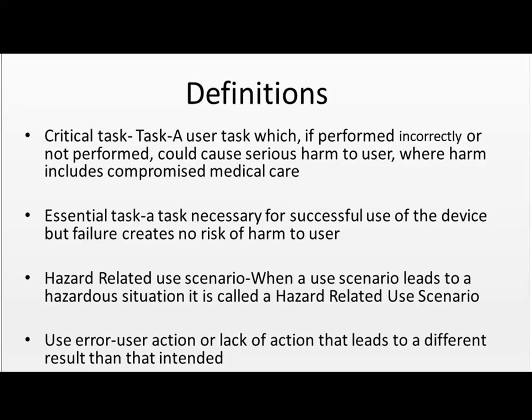A hazard-related use scenario. If a use scenario leads to a hazardous situation, it's a hazard-related use scenario. Use error: user action or lack of action that leads to a different result than that intended.